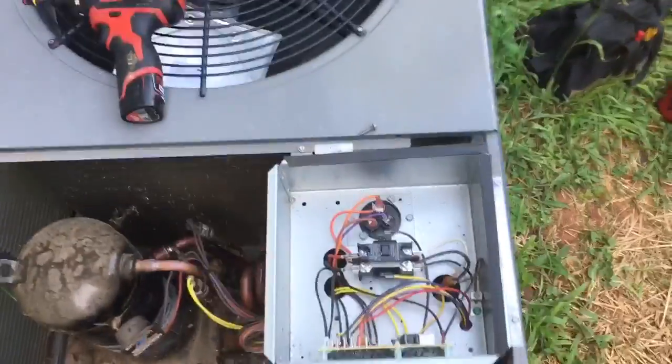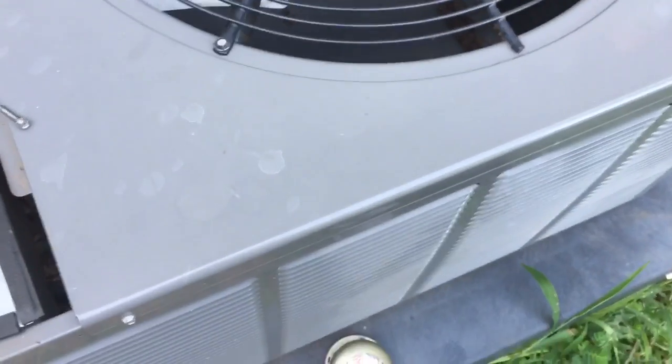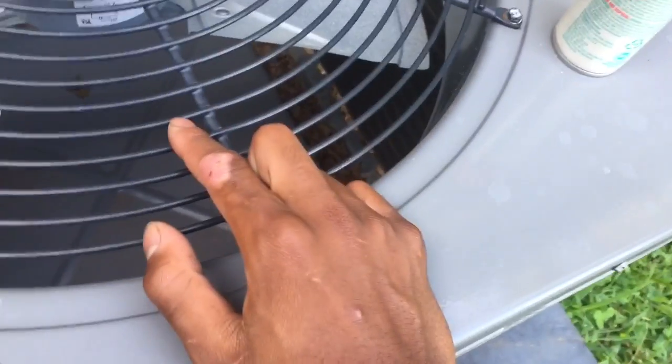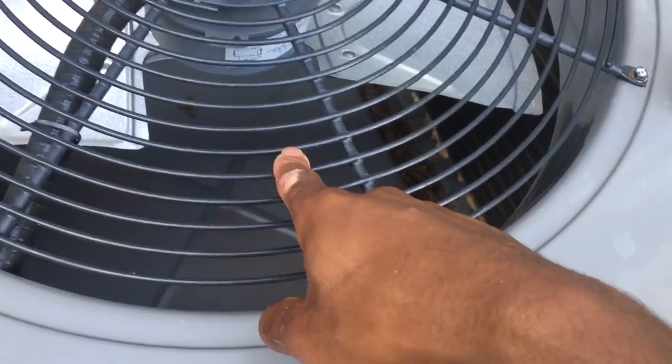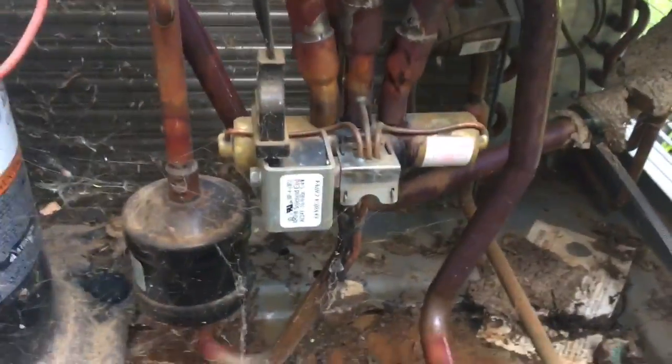Now, what controls the defrost cycle? Well, a defrost control board and a reversing valve. Okay, now what is a reversing valve? Let me just open this up. Boom, there it is. It's just in a different position. Most reversing valves will be sitting right in the middle, usually about where the compressor is. But for these Rheem units, they sit in this compartment over to the left or right, whichever way it's facing the line set going in. So here is your reversing valve.